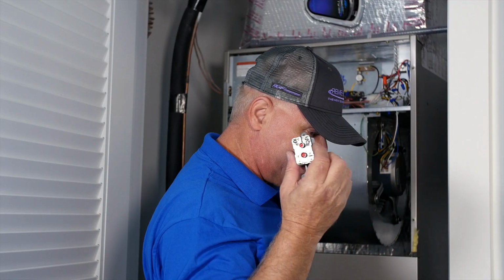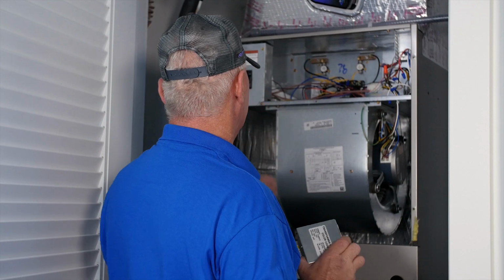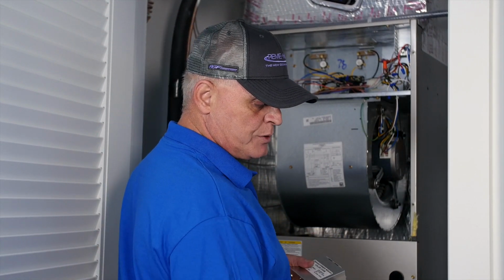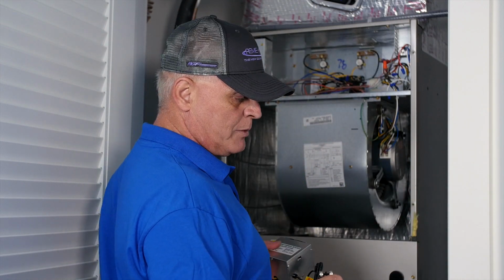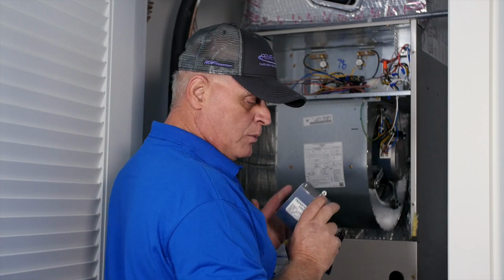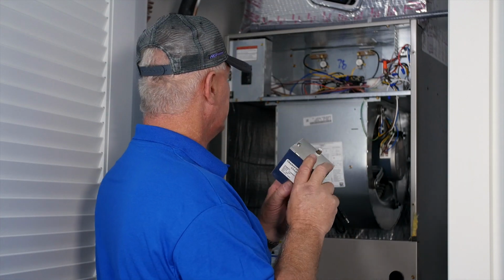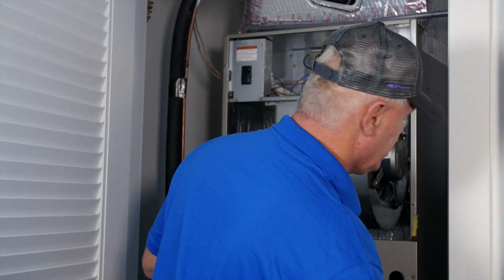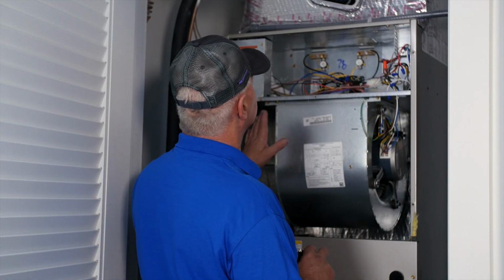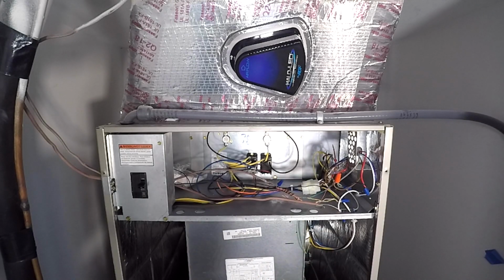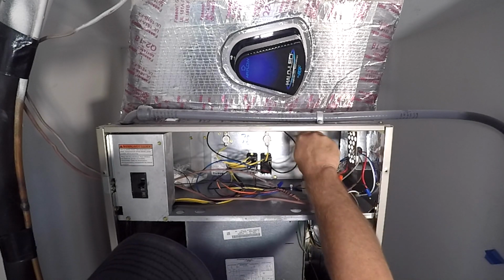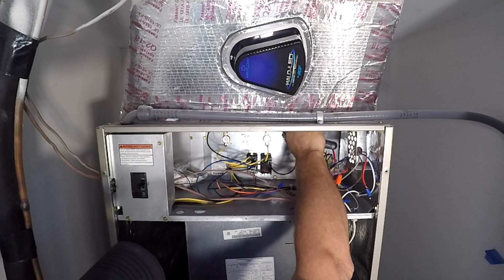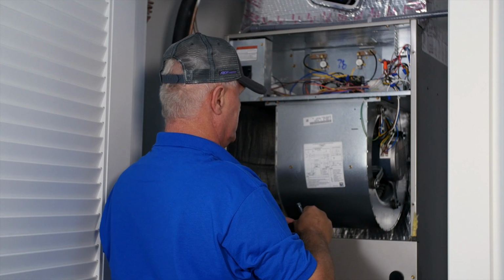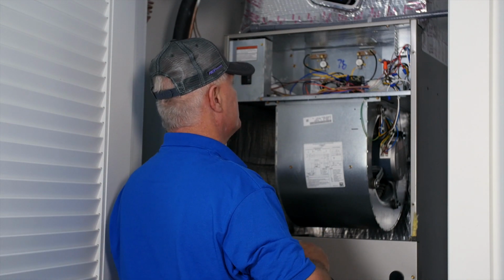So in this particular unit, we are going to use our relay, our 2-position relay, which has the normally open and normally closed contacts. We're going to use our transformer which comes with the unit and power it up through the unit itself. We're going to use the relay to cycle the power on and off for the transformer as the blower turns on and off. So we need to find a position to mount both the transformer box and the relay. As far as the relay goes, I am going to use one of the existing holes here in the air handler to mount the relay. I'm only going to use one of the holes in the relay, but alternatively it would be much better to use two of them.